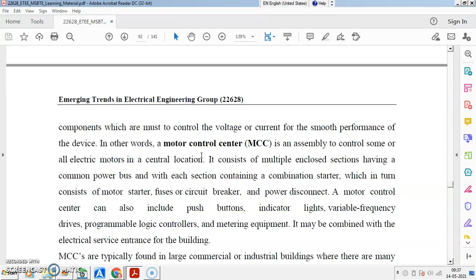A motor control center can also include push buttons, indicator lights, variable frequency drives, programmable logic controllers, metering units, protecting units. It may be combined with the electrical service entrances and like this. So a motor control center is typically found in large and commercial buildings where many motors are required to be controlled. You can control these from a central location, and you may have all the signals related to the motor available at a central unit. So the concept of the motor control center is an assembly for control of many machines at one place.